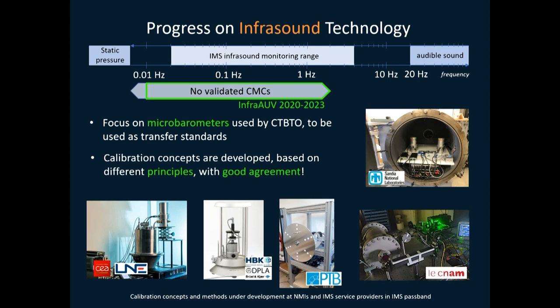But now we need to cover the part in between. For our applications we use microbarometers, which are quite different devices from microphones, meaning we need new methods to calibrate them so they can be used as transfer standards. Calibration concepts are being developed based on different principles by many NMIs and IMS service providers. Through the cooperation within the InfraAUV project, several comparisons are already being organized that show good agreement among all these principles and concepts of calibration. This gives good hope to quickly have CMCs covering the part of the range that is currently not covered.